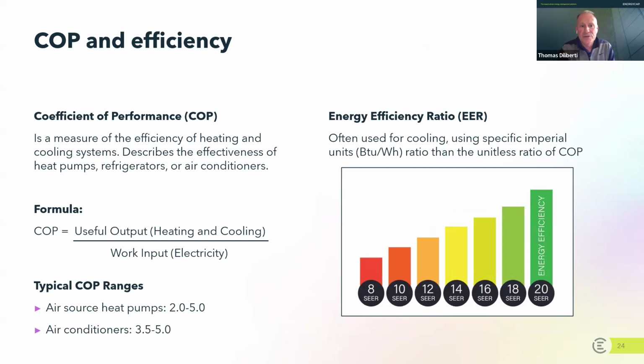I think this is my last slide of new material. I wanted to introduce you to COP, or coefficient of performance, and energy efficiency ratio. These are two terms in the industry used to describe how efficient a piece of equipment is. COP is simply a fraction looking at how efficient the object is. Typical ranges for heat pumps are between 2 and 5, and for air conditioners it's 3.5 to 5. Ultimately, it's an indicator of efficiency.